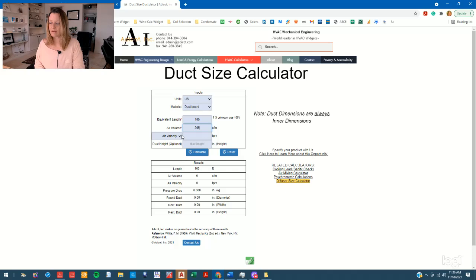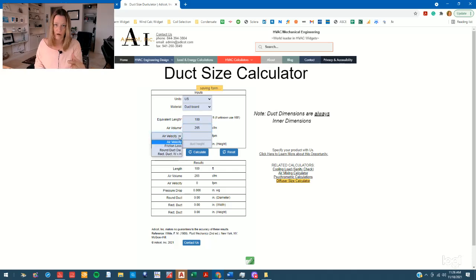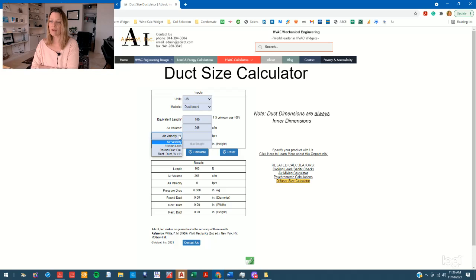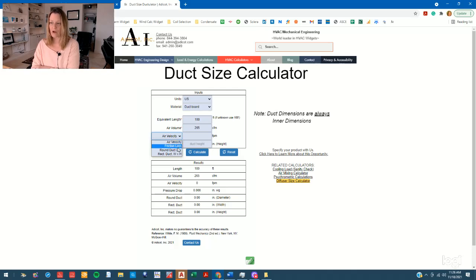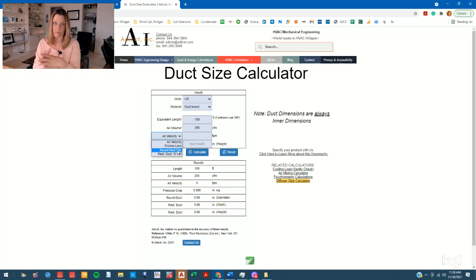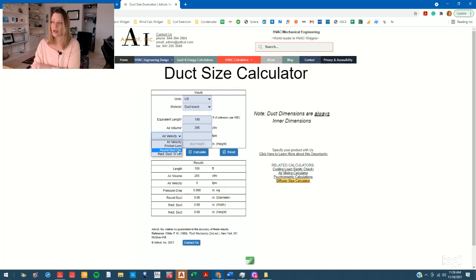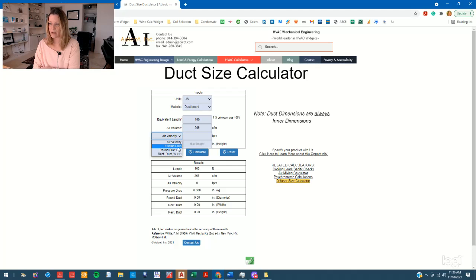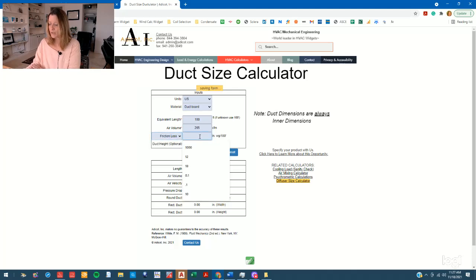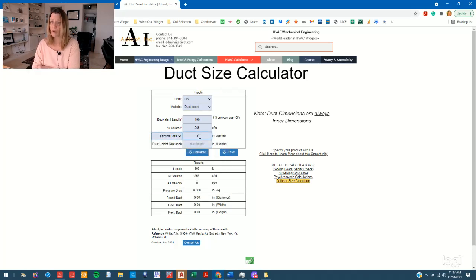You also have to enter another variable, which would either be velocity of the air that you want to design for, the friction loss that you want to be constrained by, a duct diameter, or width and height of the duct. So for this case, let's be constrained by friction loss, designed for 0.1 inches per 100 feet.